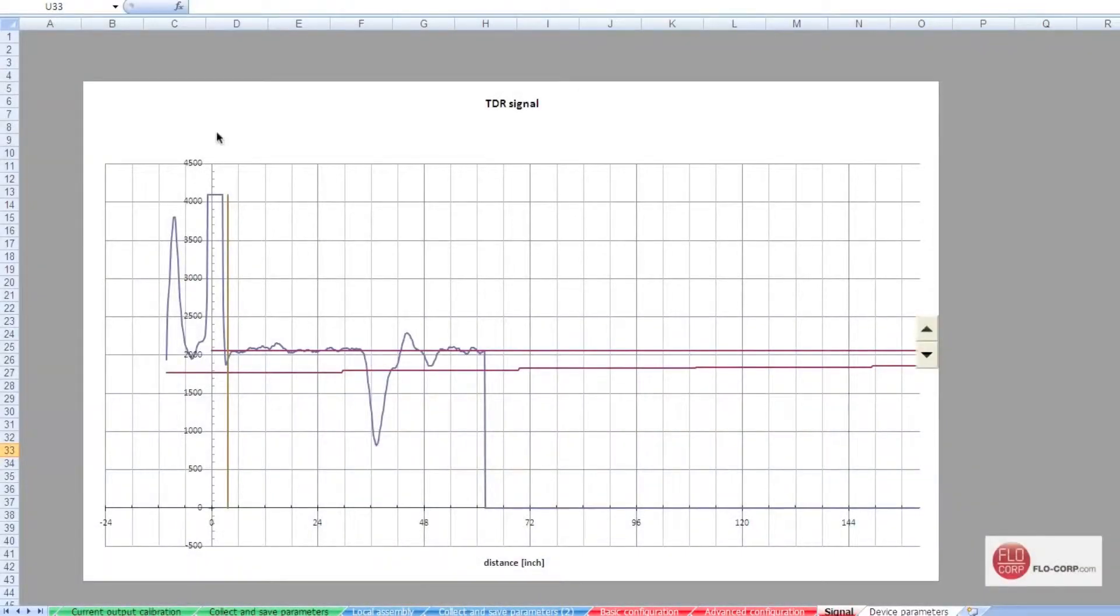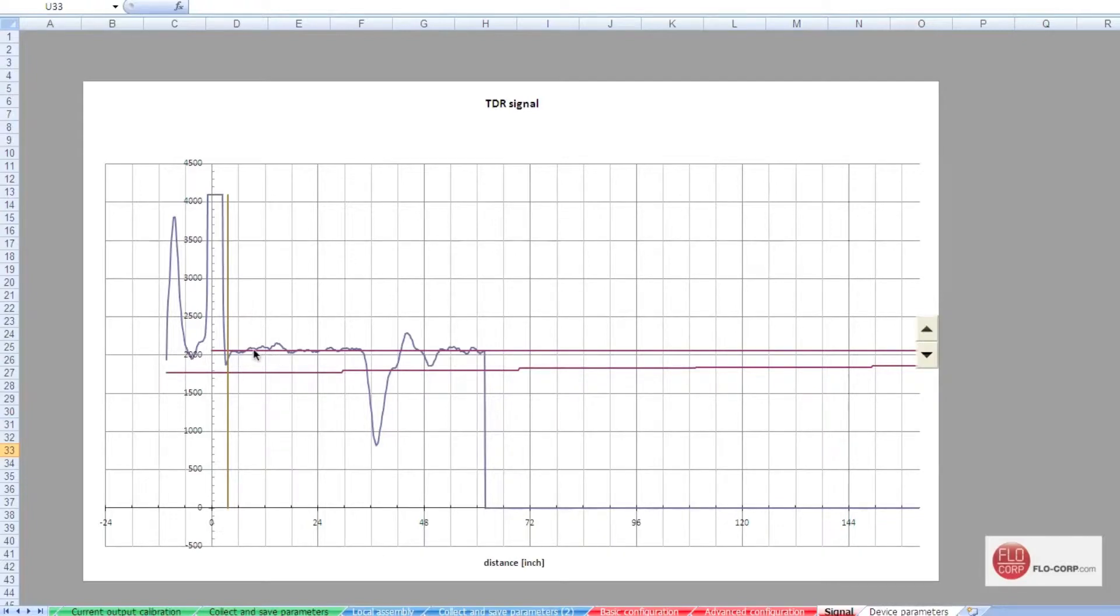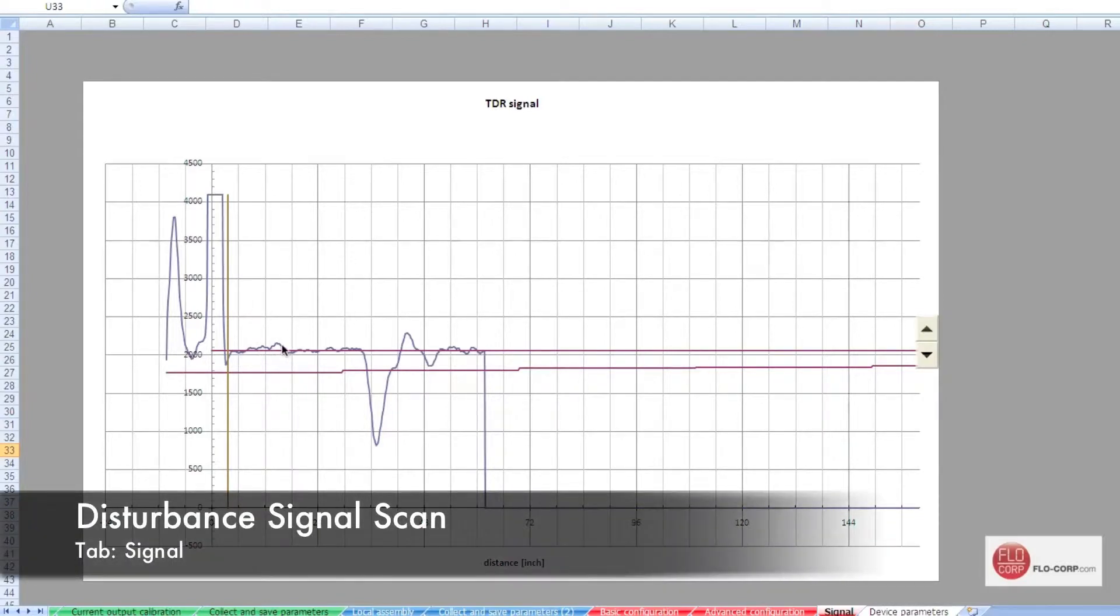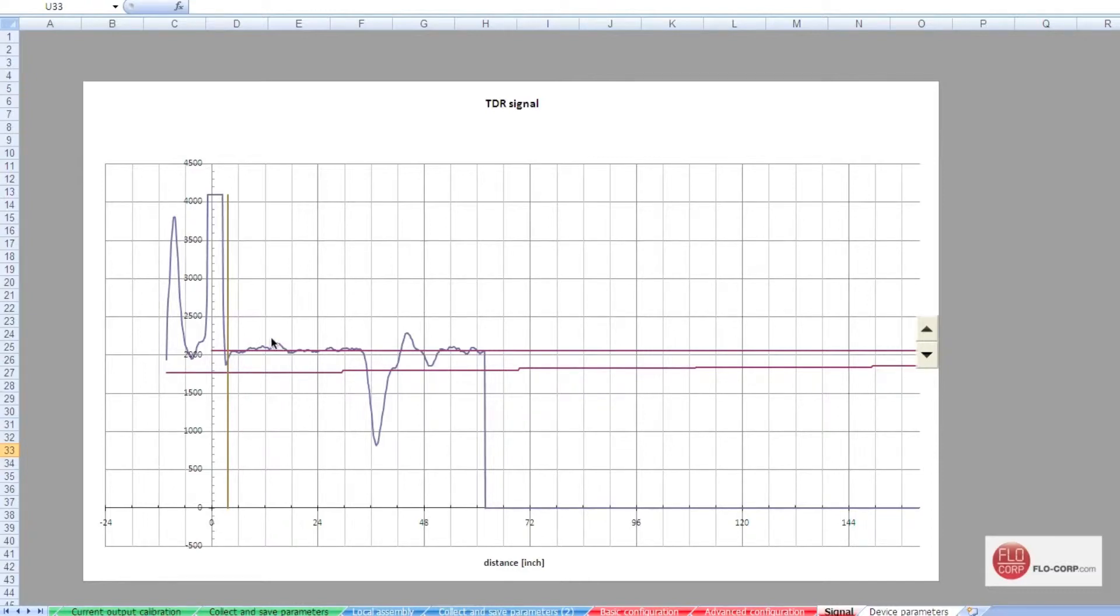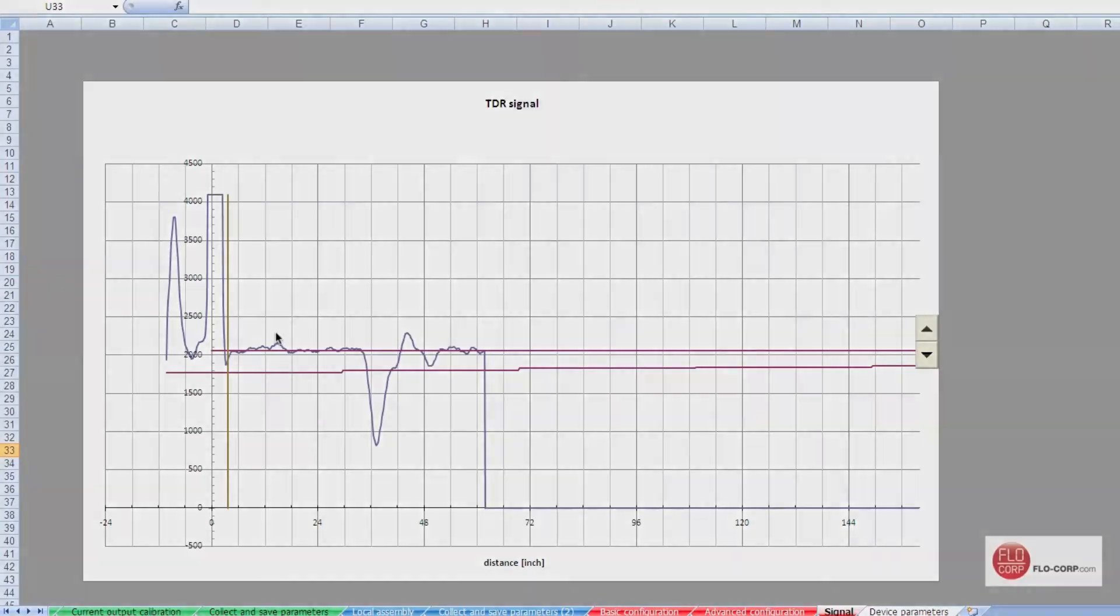Let's examine a different signal. When examining this signal, the first thing we notice is that the positive pulses are removed. This is because we've implemented the disturbance signal scan. The disturbance signal scan is a powerful disturbance signal suppression feature of the Tracer 1000. The sensor scans its entire probe length for any disturbance signals in the application that could potentially be misinterpreted as level readings, memorizes them, and suppresses them during operation. That way, the Tracer 1000 only recognizes the actual level signals caused by the liquid to be measured.